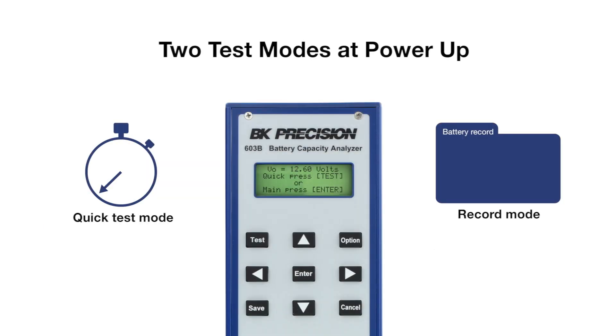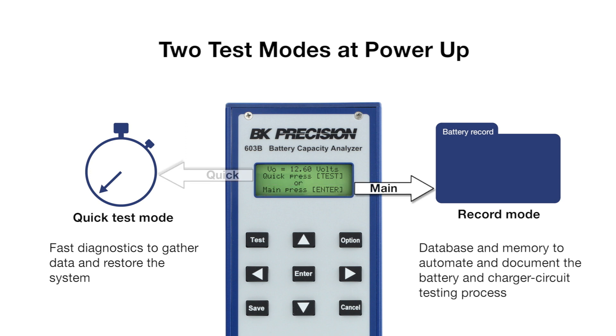The 603B features two test modes. Quick Test Mode, as the name implies, provides fast diagnostics to help technicians gather data and restore the system. The test results are displayed on screen but are not stored in internal memory. Record Mode uses the 603B's internal database and memory to automate and document the battery and charger circuit testing process.